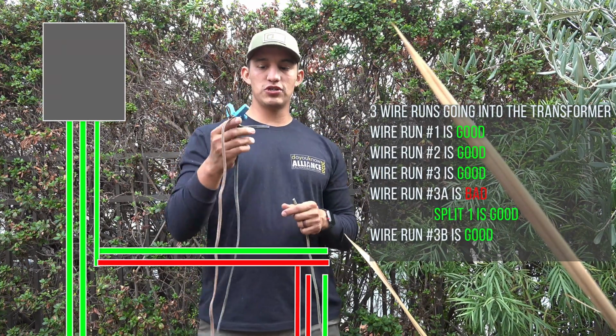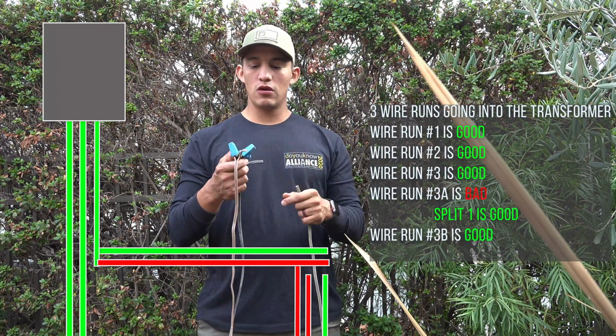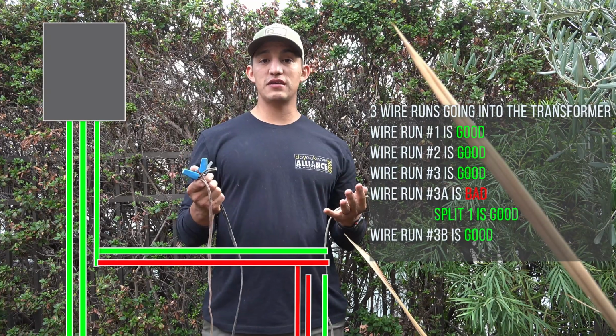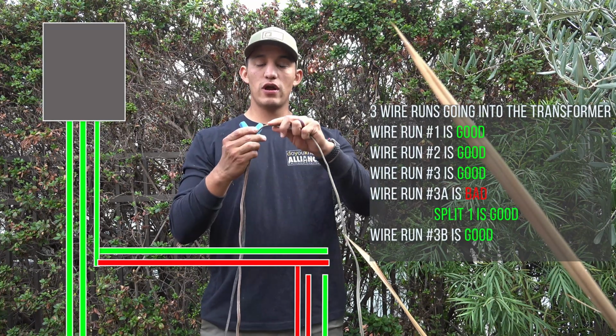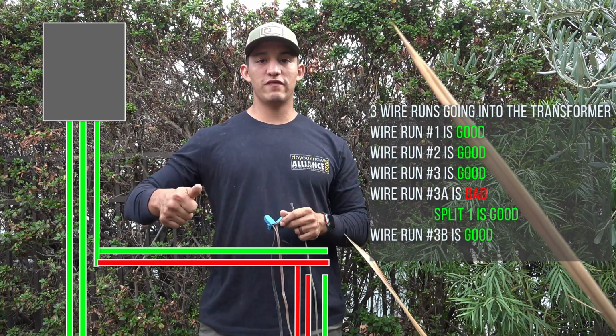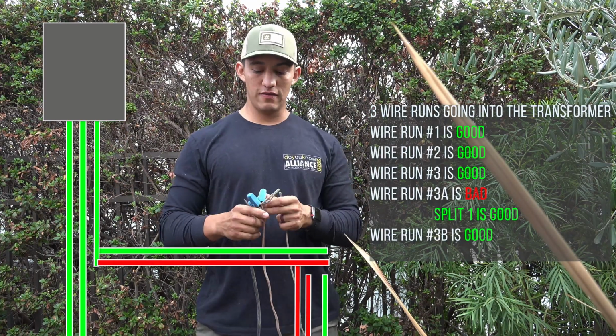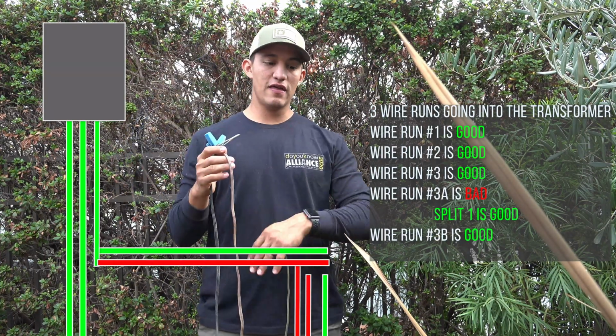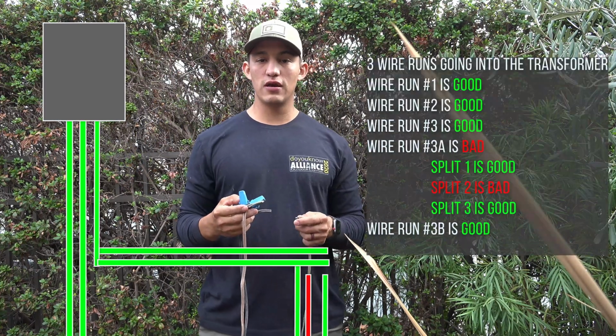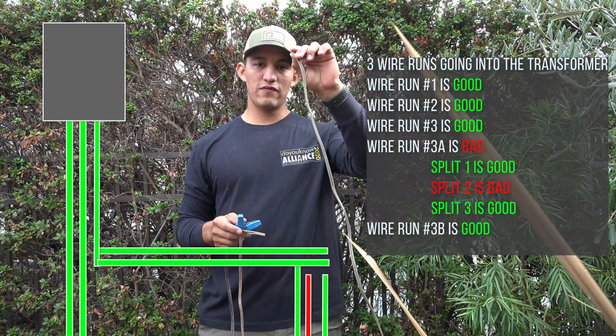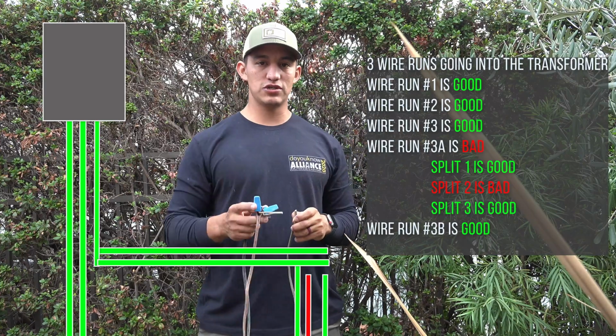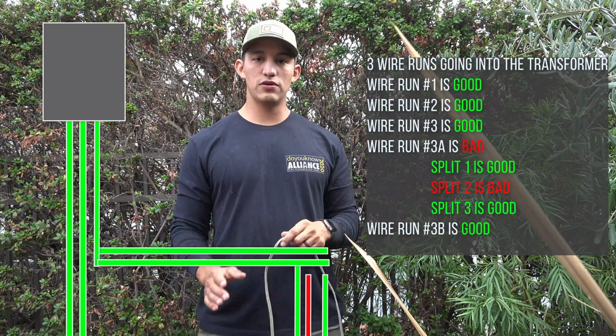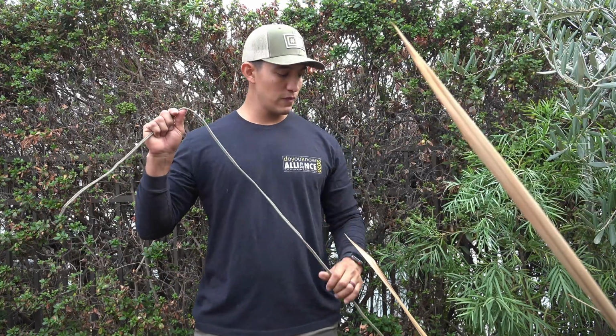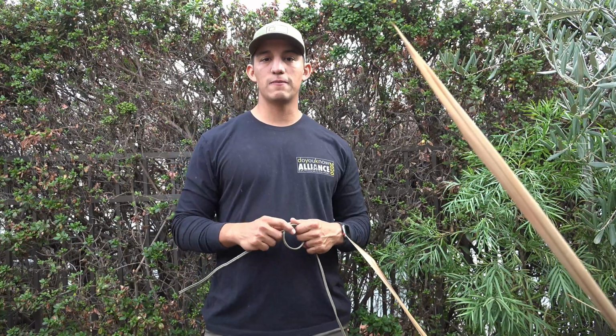Here's what we got. At our junction, we cut the black wire and that wasn't the issue. Then we cut this brown wire, turned the transformer back on, and the wire run that's still intact stayed on. That tells us the short came from the second wire we cut from this junction. Now we'll trace this wire and try to find the issue further down the line.